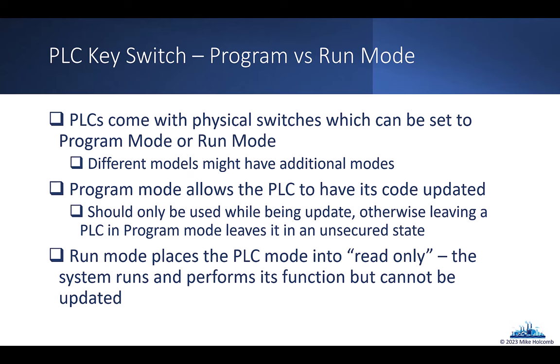So another thing I wanted to mention before we move on from PLCs is that PLCs have a key switch. Sometimes on more expensive models, it's literally a physical key that you insert into a key switch and turn. A lot of times, like on the Click PLCs, and I have some expensive Schneider and Siemens equipment, it's just a little dip switch, a little switch that you flip. The idea is that PLCs usually have at least two modes, generally one called program mode and one called run mode. Or the idea is one is read-only mode and one is read-write mode.